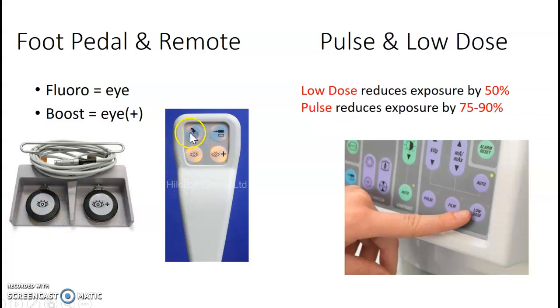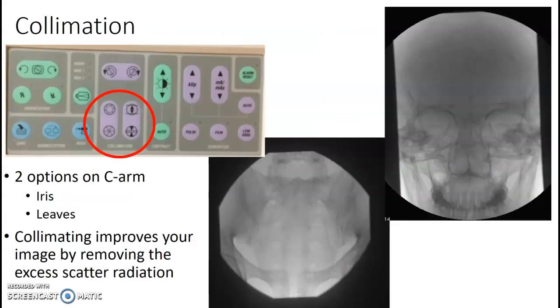But the remote also has a swap or a save image button if you need it. And then pulse and low dose you'll find on the C-arm control panel. Low dose reduces the patient exposure by 50%, and pulse reduces exposure by 75 to 90%. In certain cases, we'll use pulse and low dose. For us, every fistulogram case, you can automatically put it on pulse and low dose without even having the surgeon ask you for it.